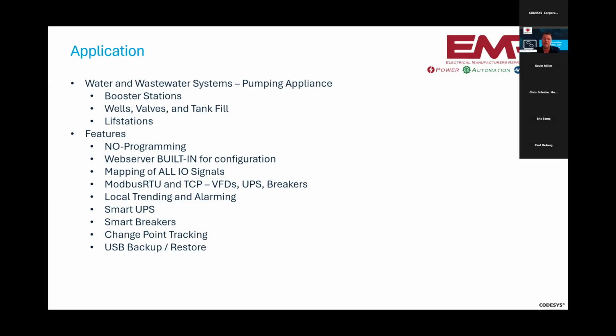And then also with this, we're doing local trending and alarming, which we'll show from the WebVisu. And we're trying to help the operators out. So one of the things here is a smart UPS and smart breakers, so that before they go to the job site, before they go and see what has happened, they know what the power is, what breaker might have tripped, why it tripped, short or an overload, and they can reset it through their own SCADA system.